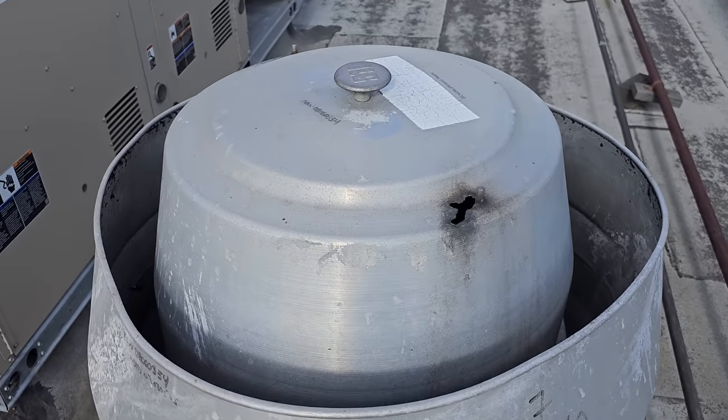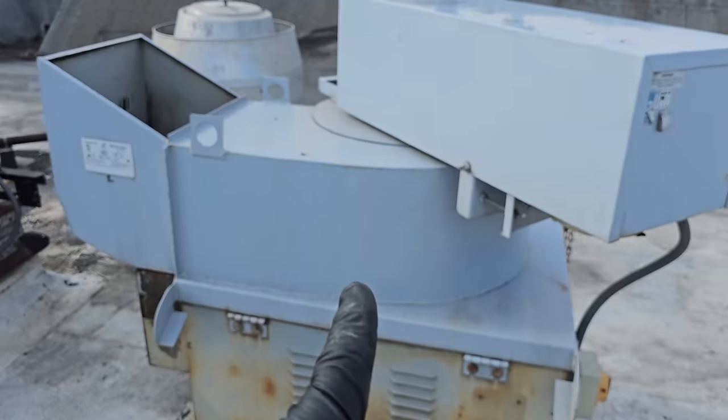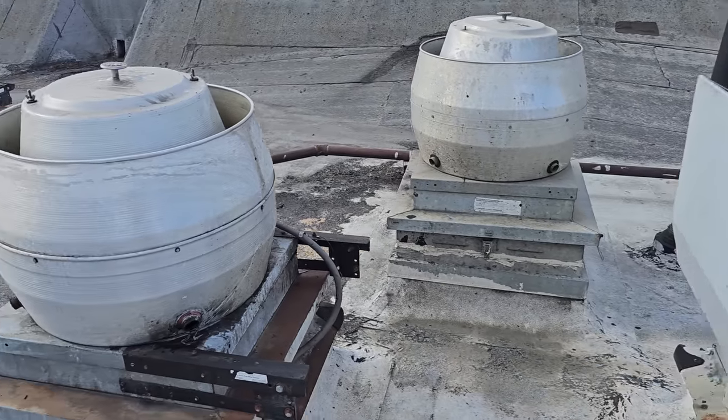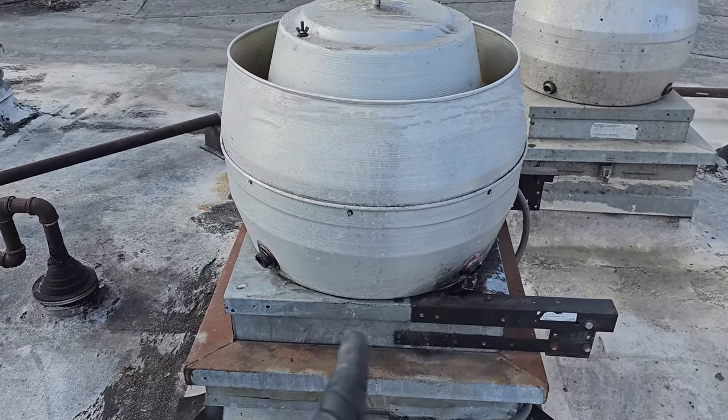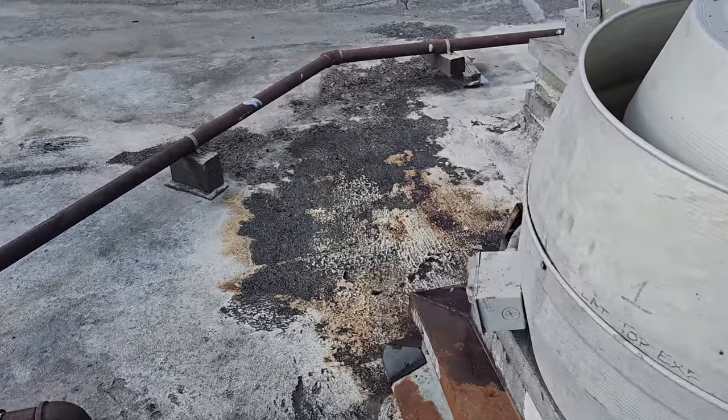You can see the covers are completely rotted out. They're old, they're beat down. And then this fan was replaced a couple years ago, so we'll just change the pulleys. This fan just needs to be cleaned.